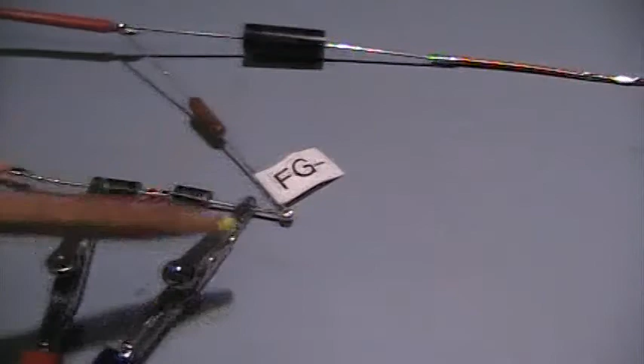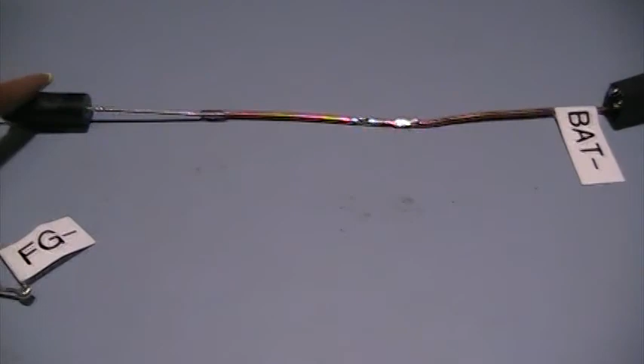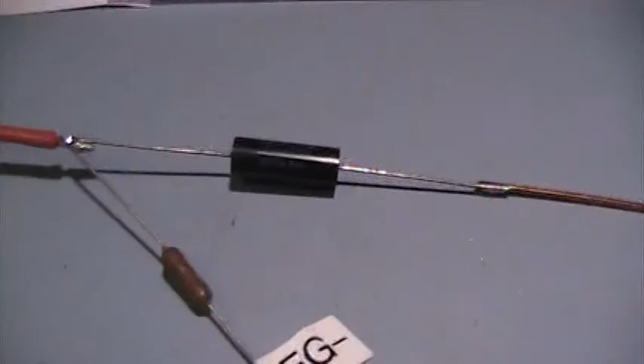That's why trying to do a power measurement way over here on the other side of 20 feet of wire for your CSR - the CSR is probably not so bad as long as you are right tight against the body - but the battery voltage needs to be taken as close as possible to the battery. And the only reason we can't use this CSR when measuring the batteries directly is because we can't put the references at the same place. That's why we had to install a second CSR over here by the batteries.